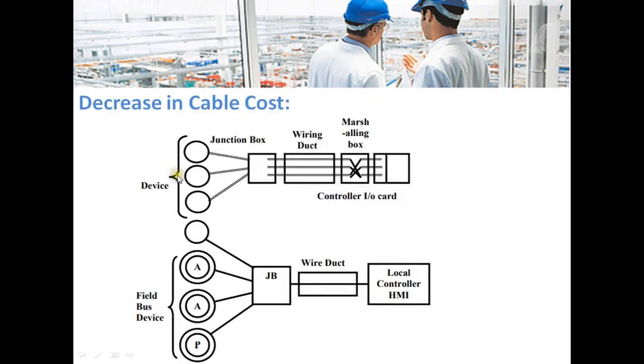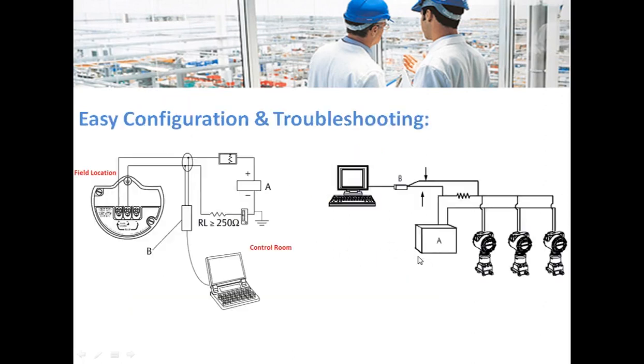Fieldbus devices decrease cable cost. In a 4-20mA system, a separate cable needs to be routed to the control room for each device. Whereas with fieldbus, devices can be connected in bus or star topology, and a single cable goes from the junction box to the control room.